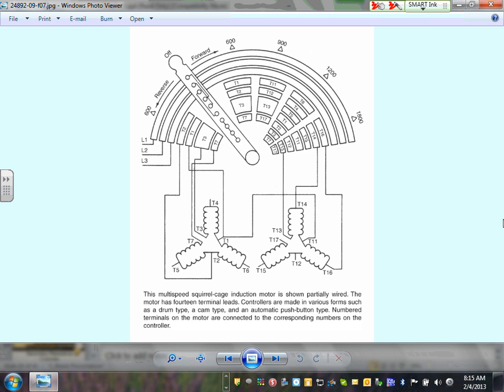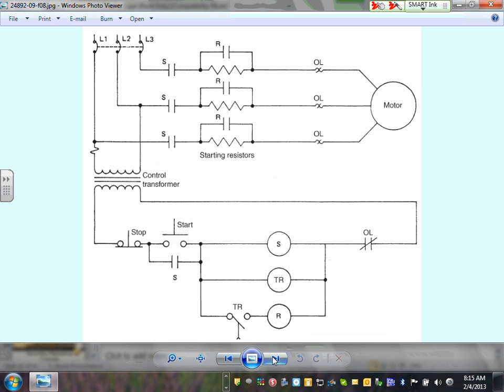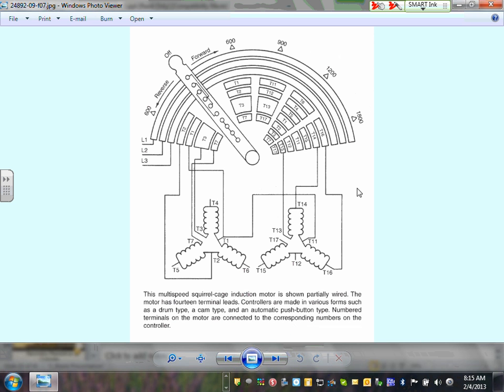Any comments, any questions? This has been solved by one little thing, the VFD. To have this, it has to be a special motor that runs at 4 speeds, and you can see the speeds are half of each other, right? So you have, let's say, here 600, 900, 1200, and what's the other one? 1800? 1800. And only in steps. I can solve the problem, instead of this type of motor, now with my VFD. Okay, so I'm going to show you that one anyway before we get into that.